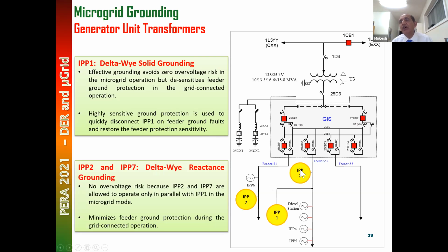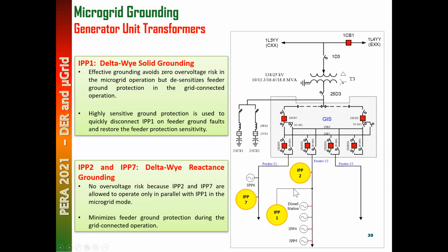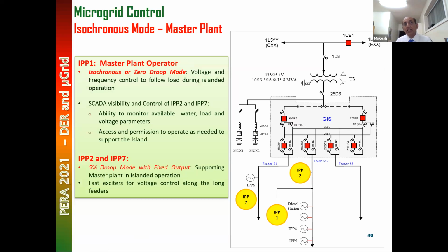These two generators are not expected to serve in an islanded mode, and they are not going to survive as an island. They are impedance grounded using the method which I told you. They could serve if we wanted it, but we have decided they were not going to serve in a microgrid as a standalone. 2 and 7 will be connected in a microgrid mode only if 1 is connected, which will provide a very good effective grounding. Effective grounding will come from 1, as 2 and 7 are impedance grounded, and as long as 1 is there, we will have very good grounding. Very important thing.